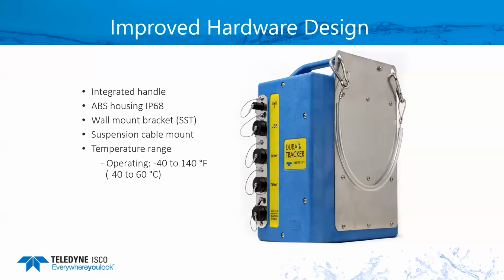So a couple other improvements that we've made. We've had some improved hardware designs. As you'll notice, we have the integrated handle at the top. So it's all molded into the plastic, so it makes it really easy to carry it around from site to site. It's made out of ABS plastic, IP68 rated, just like the 2100 system. We've added a stainless steel wall mount bracket. So even though it's the portable one, you could hang it on a wall, or we can use the suspension handle so you can then easily hang that from a manhole rung or to carry it. And the operating range on this is down to minus 40 degrees Fahrenheit up to 140 Fahrenheit.